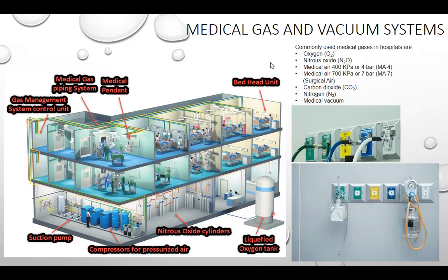Meron tayong oxygen, nitrous oxide, medical air 400 kilopascal or 4 bar, which is MA4, or medical air 700 kilopascal or 7 bar, MA7, which is surgical air. So ito yung common na medical air is yung 4 bar lang. Okay? And PSI, later malaman natin yan.